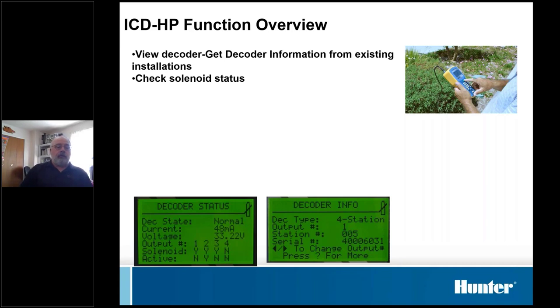It'll give you status information, like the decoder state. Normal is what you're hoping to see. It could tell you that it's damaged. It could just be blank. It'll tell you the amount of current that's being drawn through that decoder at the given time. It'll tell us the voltage at the decoder. And then also tell us if there's a solenoid attached to the outputs and whether that solenoid is active at the moment or not. This is all really helpful information when you're troubleshooting systems.